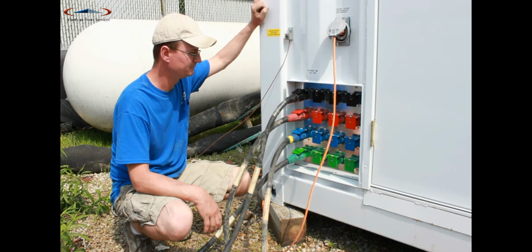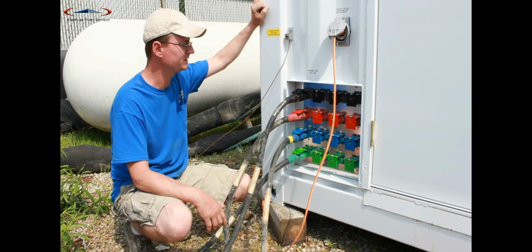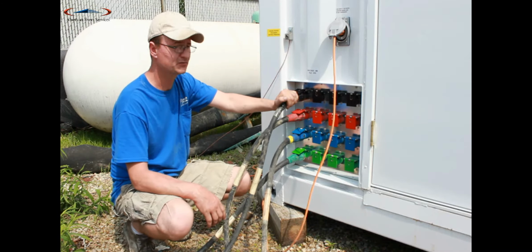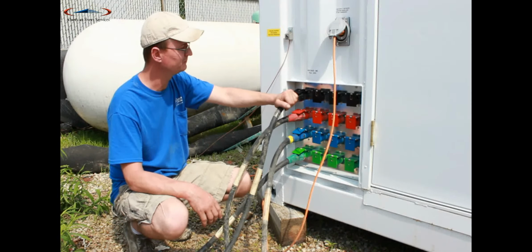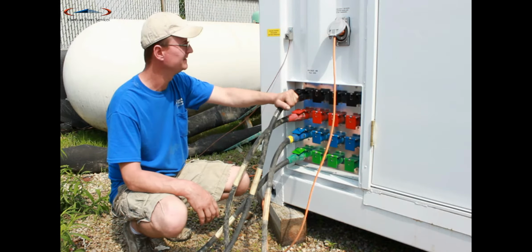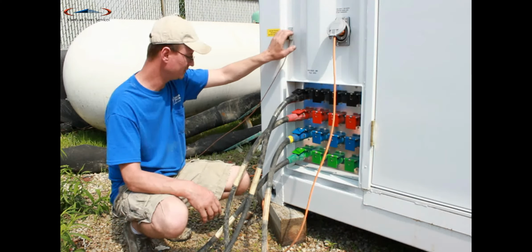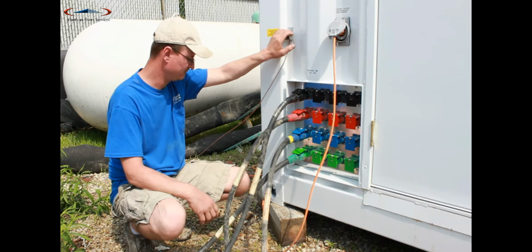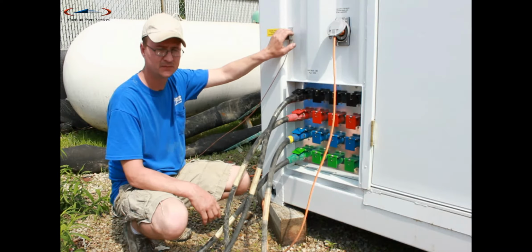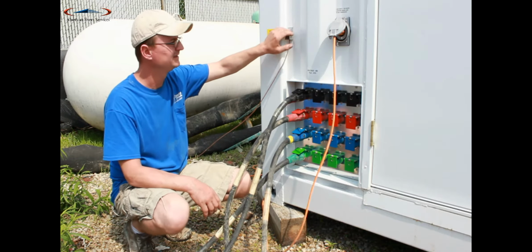Before you put any power to this thing, a couple things you need to do. Make sure you don't have any power. Plug all your 4-aught cables in. We've got a grounding lug here. Got to ground the box, the unit, to a grounding rod.